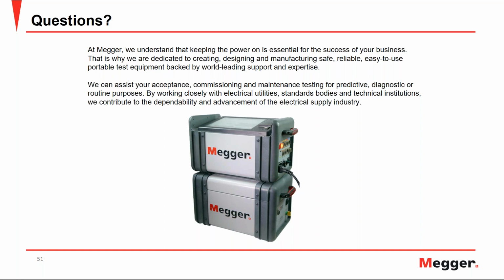Thank you, Dinesh. My next question I'm going to be sending over to Daniel Carreño. Daniel, in regards to NBDFR, how many samples should be taken and at what frequencies? Thank you, Michael. Hello, everyone. Well, there is no hard rule, if I can use the term. You typically take about 10 to 12 measurements across the narrowband, the DFR range, which is, again, as Charles mentioned, between 1 and 500 hertz.